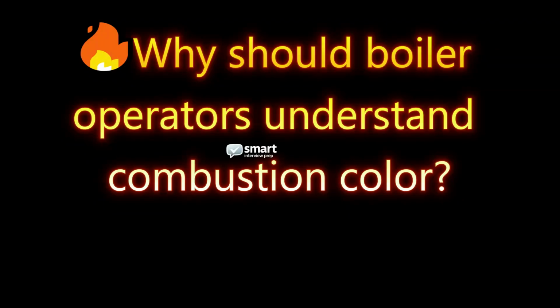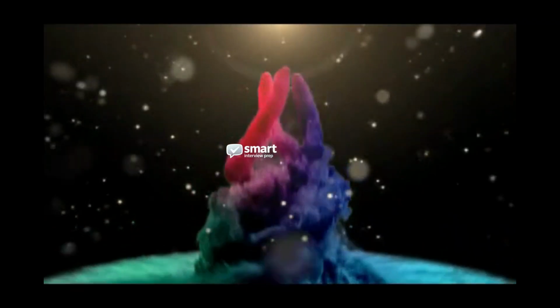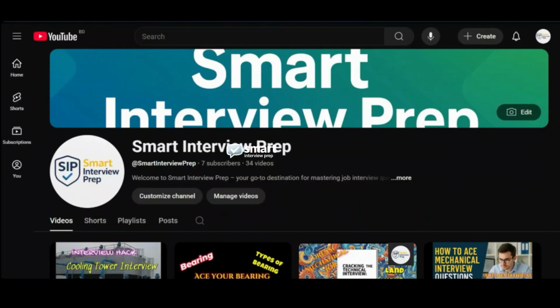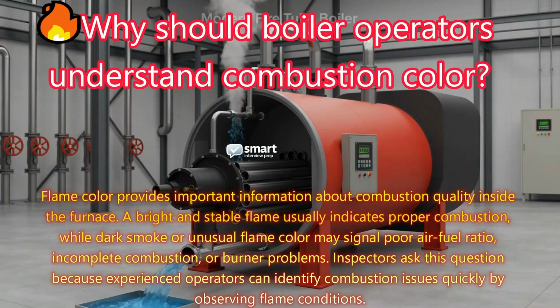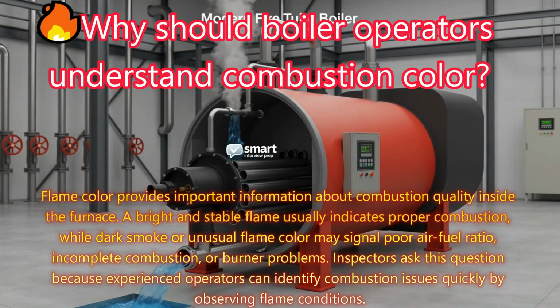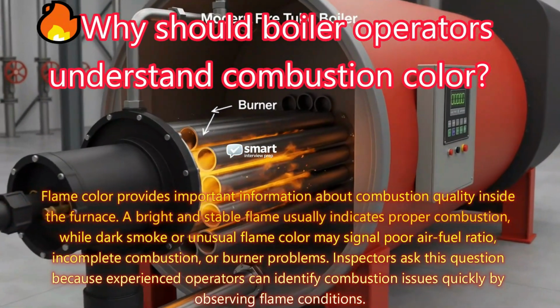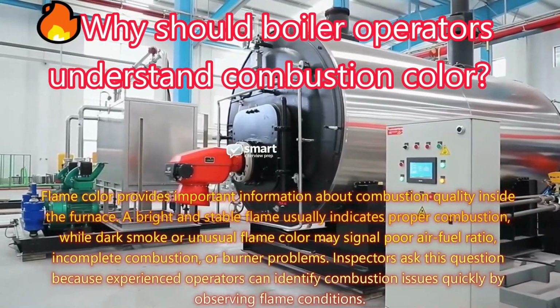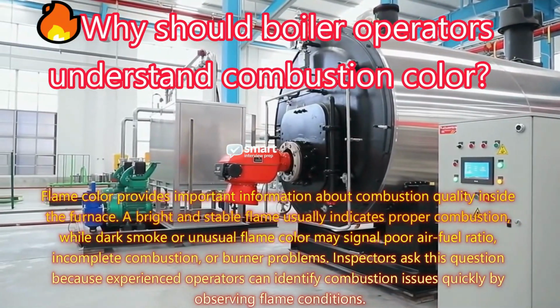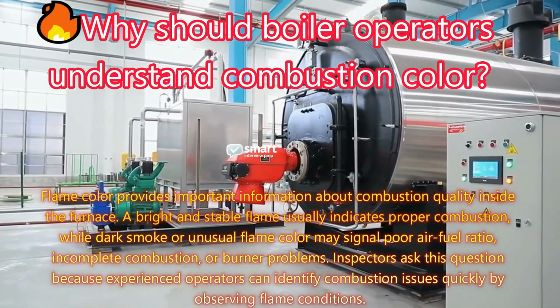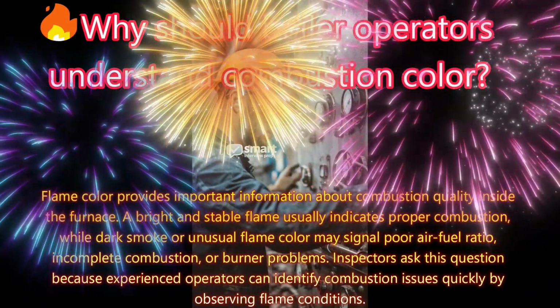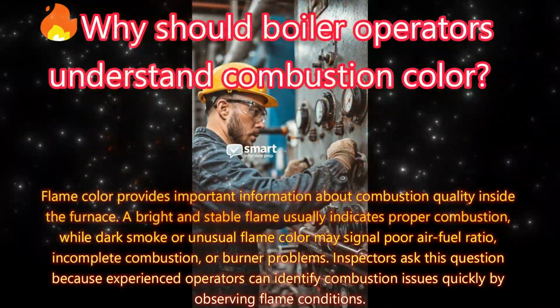Why should boiler operators understand combustion color? Answer: flame color provides important information about combustion quality inside the furnace. A bright and stable flame usually indicates proper combustion, while dark, smoky, or unusual flame color may signal poor air-fuel ratio, incomplete combustion, or burner problems.